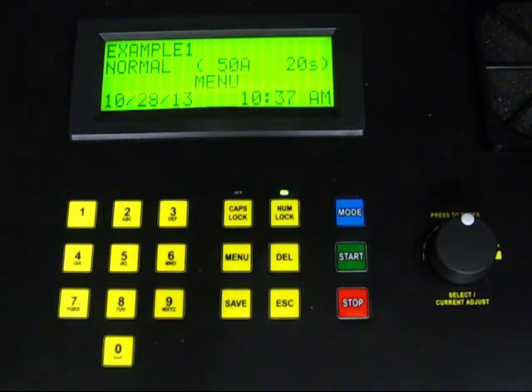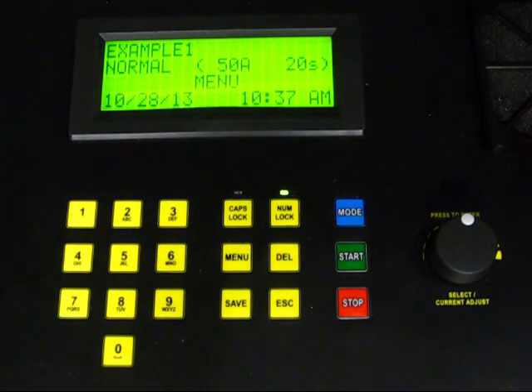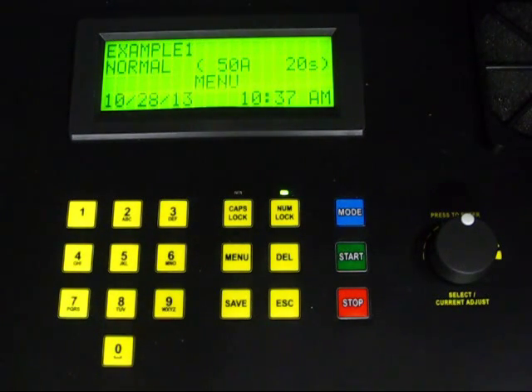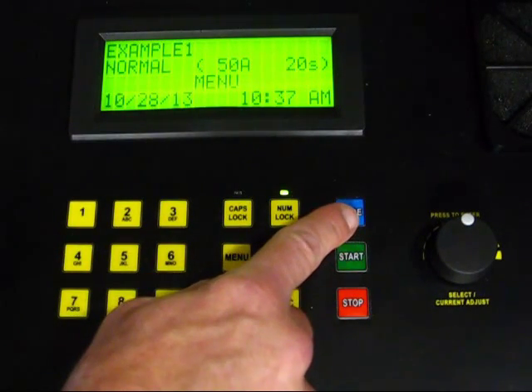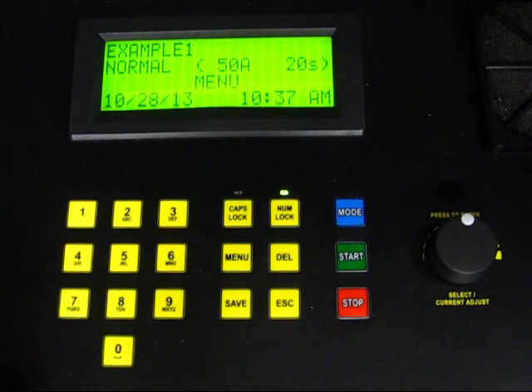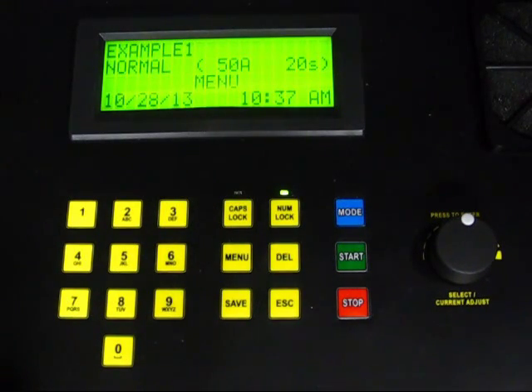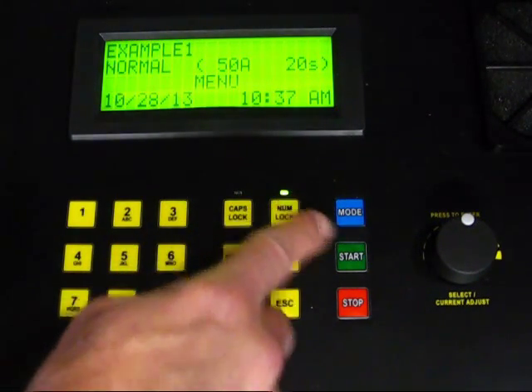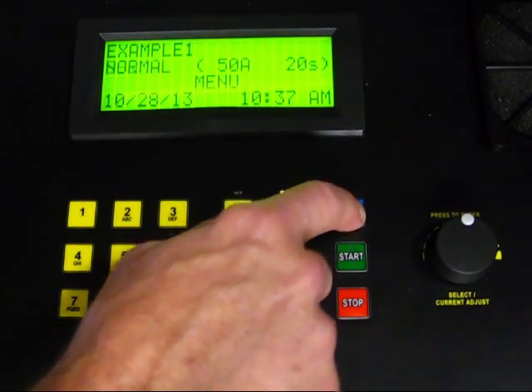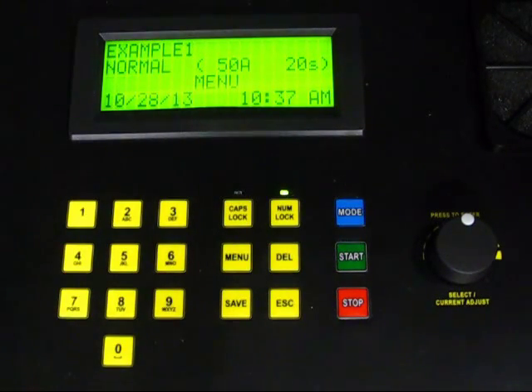The final step in setting up the test is to select the test mode. There are two options, Normal and Both Sides Grounded, represented on the display as BSG. You select the mode by pressing the blue Mode button. In our test, we will select Normal mode.